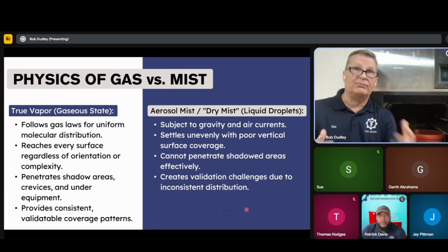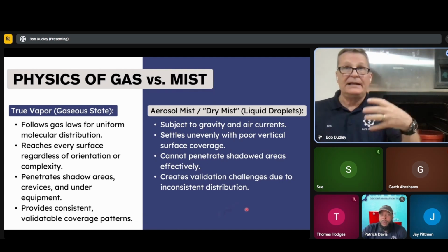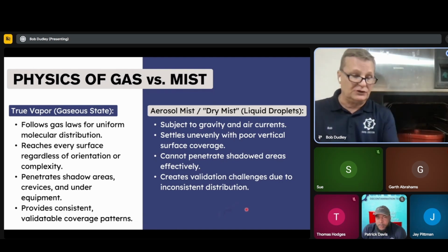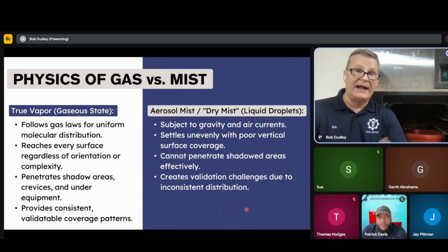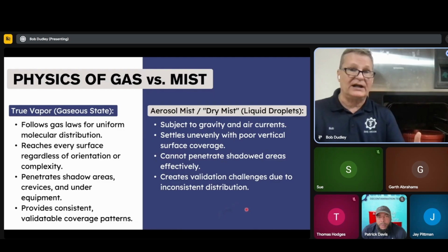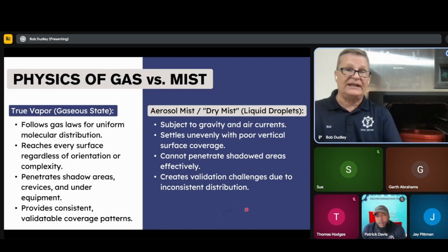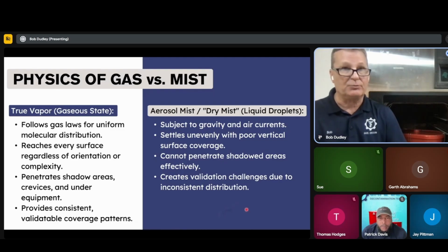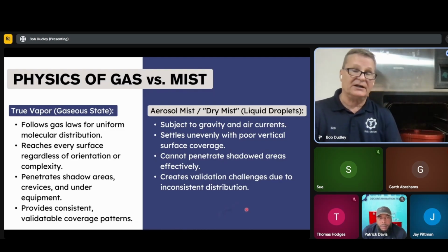I guess I'm trying to break this down so you understand it. If you look down in the pot and you looked at the actual boiling part, you'll see that it's clear. And that's what gas is. That is what is going on inside of your autoclave. It's not steam that you can see. When you start being able to see the steam, now it becomes a problem. And those in healthcare kind of understand this. When you start getting a wet mist, then they get what they call wet packs within their autoclave.